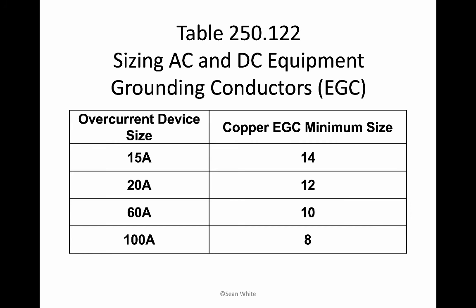Then you round up to the next common overcurrent protection device size, and you'll get that 15 amps or the 20 amps after multiplying short circuit current times 1.56. And that's because most of the time we're using solar cells where the current would be less than 20 amps divided by 1.56 or 15 amps divided by 1.56. And also, though, you might have circuits that are 60 amps, 100 amps or more for your AC circuits or bigger DC circuits, and you might be doing some of this.